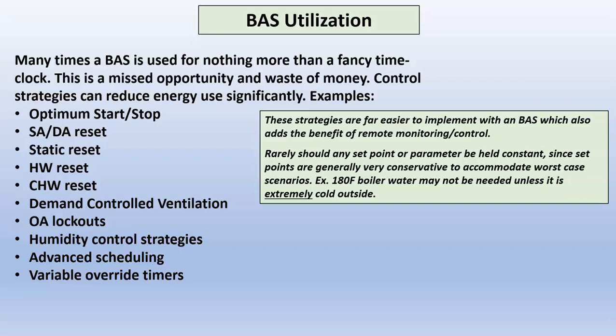Outdoor air lockouts. If you don't have these on your chillers and boilers, they almost always find a way to run when they shouldn't. I've gone into places where it's 90 degrees and there's the boiler just chugging away. You need to put a lockout on it that says above this temperature, it's off. Because if you're relying on all the other automation to do it, inevitably something's going to screw up. Same way with the chiller. I've gone to places that are 35 degrees and there's my chillers humming along. You need to put a lockout in, 40 degrees, shut off.